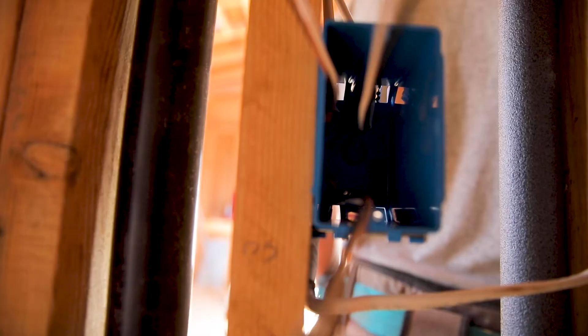The first thing we're going to do is tie all the grounds together. No matter where it's coming from, whether from the light or there's power out going to the next box, we want it to eventually go back with this power-in ground to our panel box and get grounded. So we're going to tie them all together.